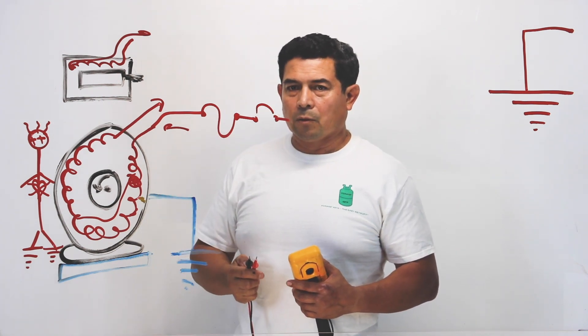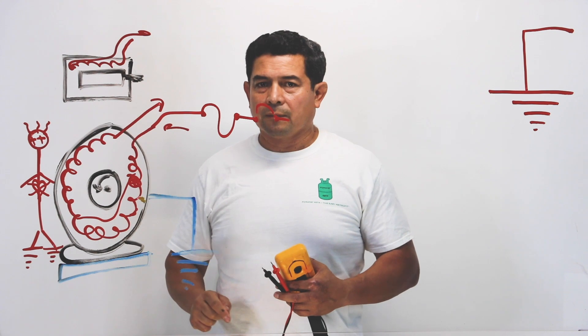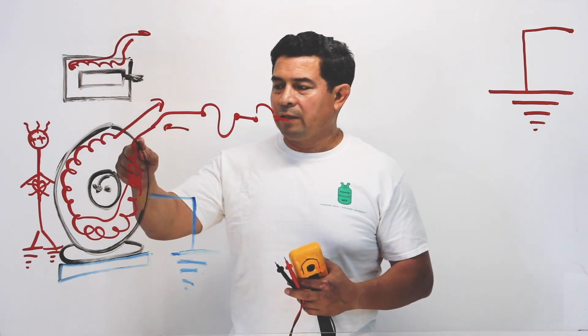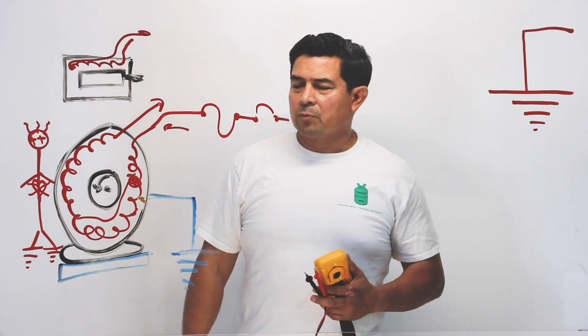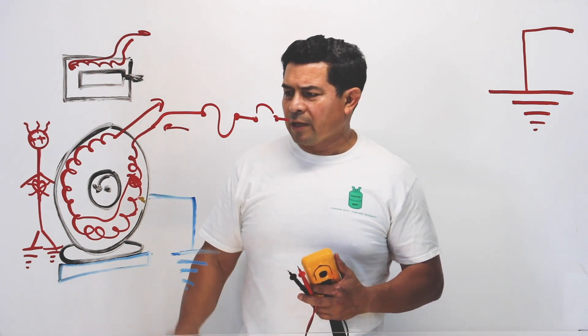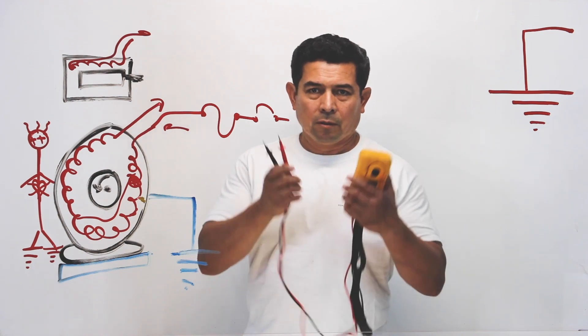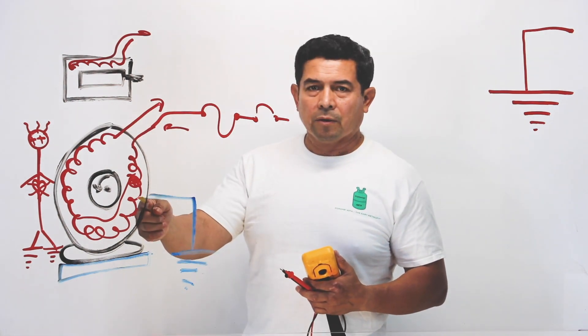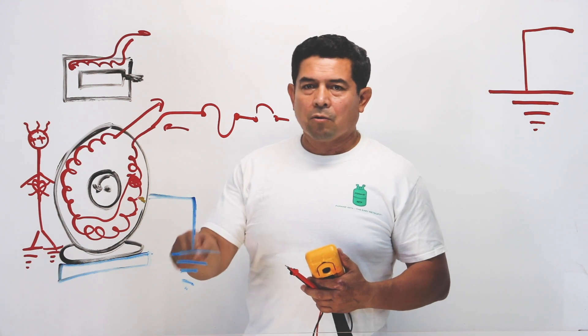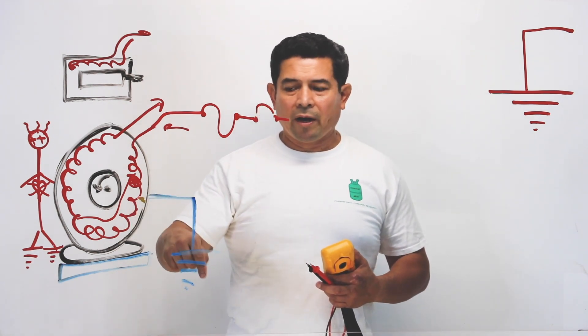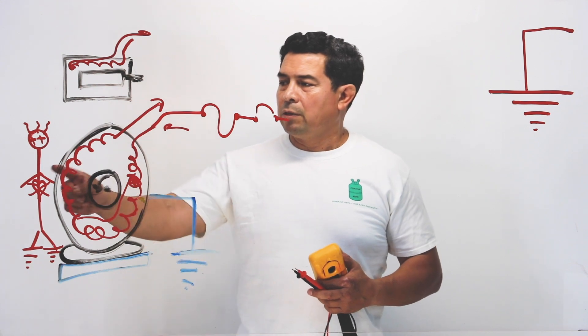To find a ground, you check for a connection from the windings to the casing. That is what a ground is. If you have less resistance between the windings, that is a short — there's a big difference between the two. If you read any ohms between the windings and the casing, you know you have a ground. Remember, that green wire — the bare wire that connects to ground — is the most important wire you could possibly have, because that wire could save your life.